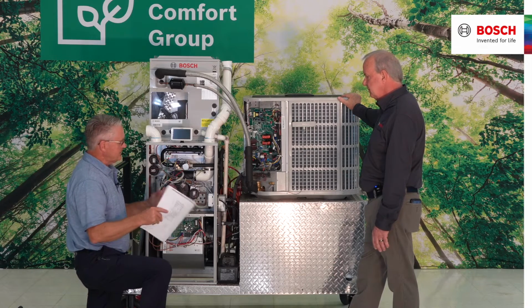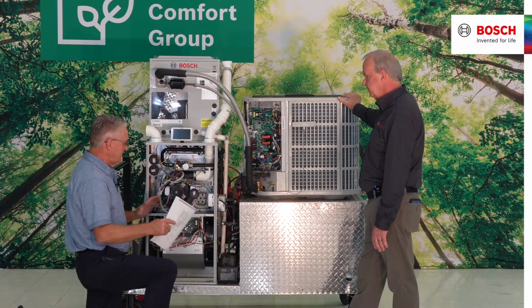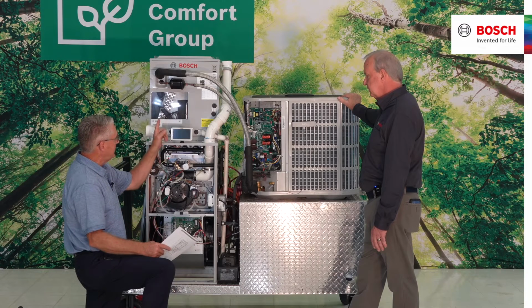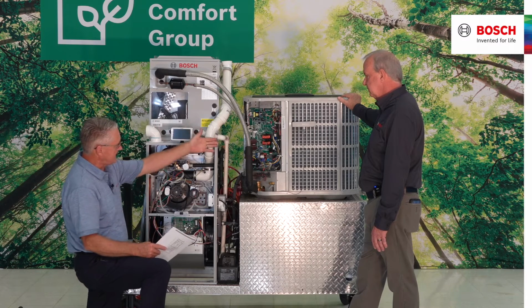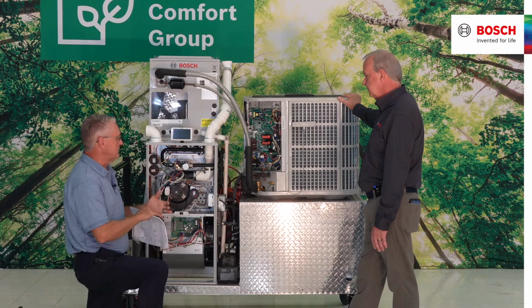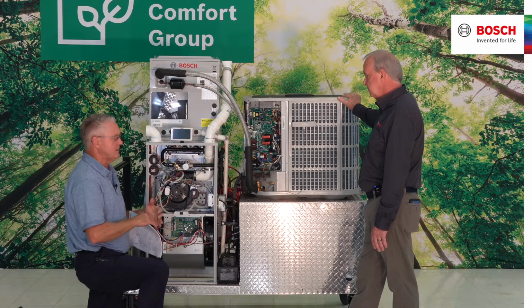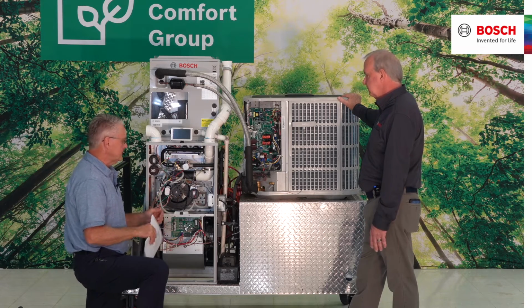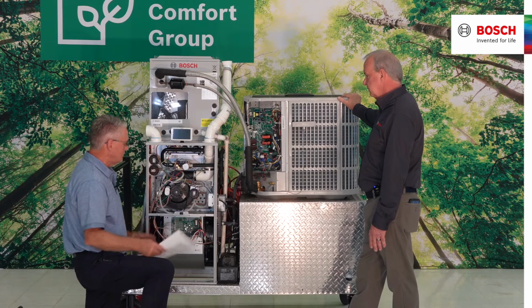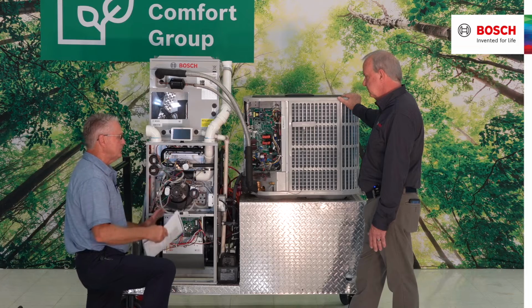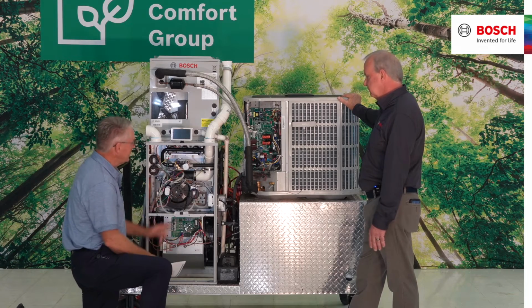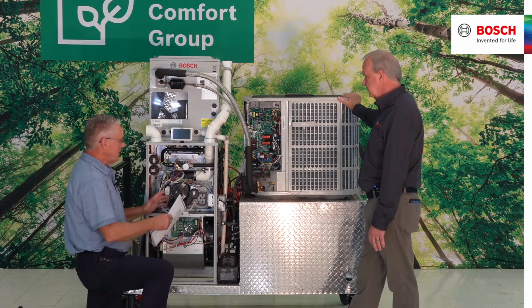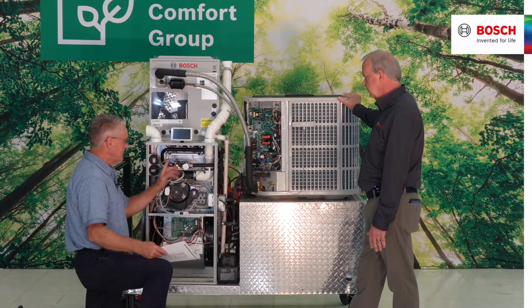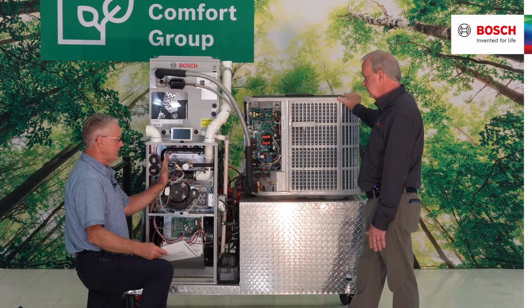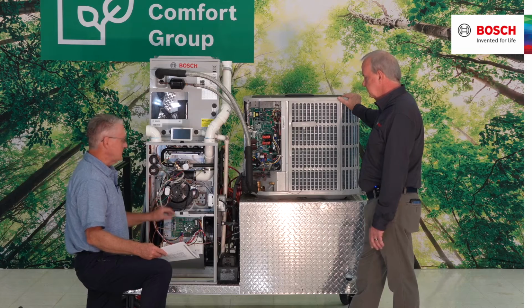Great question. The idea behind that is, when I match my system up with my IDS product, we are still looking at that 350 CFM per ton. We're still looking at, in the wintertime, a delta T, or what we would call a temperature rise from the return air to the supply air, based off of our gas pressure, based off of our firing of our W1, W2 type scenario.